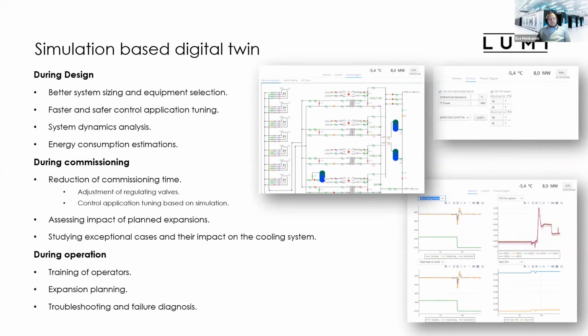This can be also used assessing impact of the plant expansion. So if the IT load increases, how the cooling needs to be adjusted if the system is expanded. And this can be also used to study exceptional cases and their impact on the cooling system. So for example, we could simulate a pump failure and that kind of things with this system. During the operation, this can be used for training of operators. This would give them the safe place to test different kind of cooling parameters before putting those into production and get understanding how this cooling works in real life. And this can be used also for the expansion planning and troubleshooting and failure diagnosis.